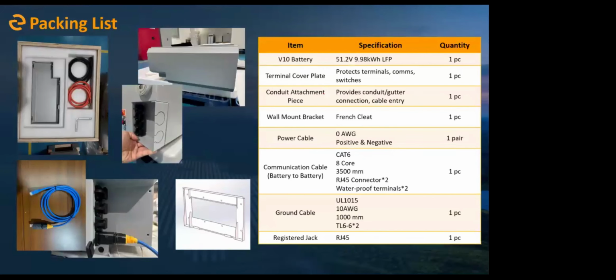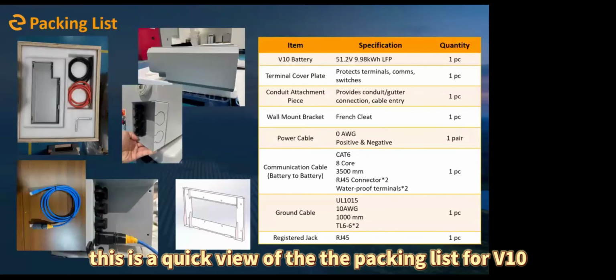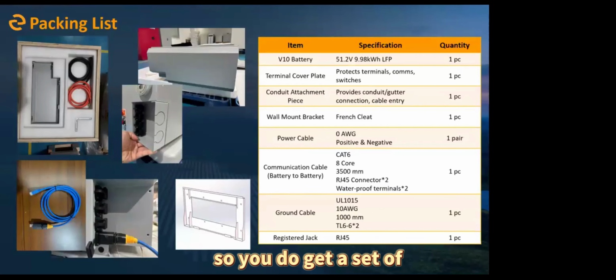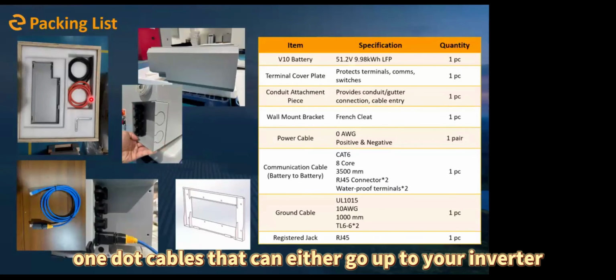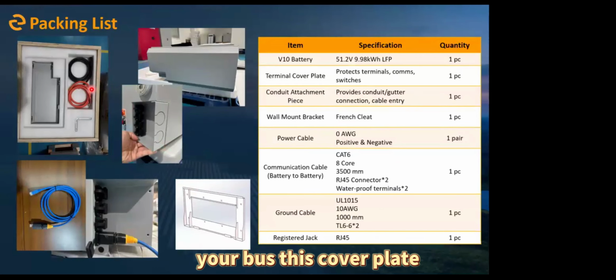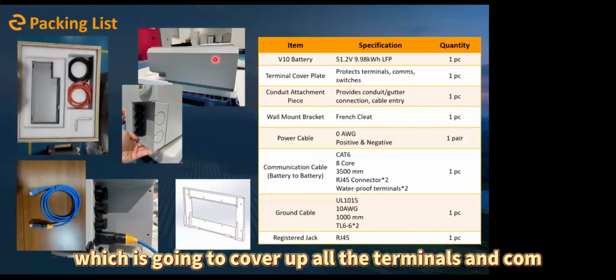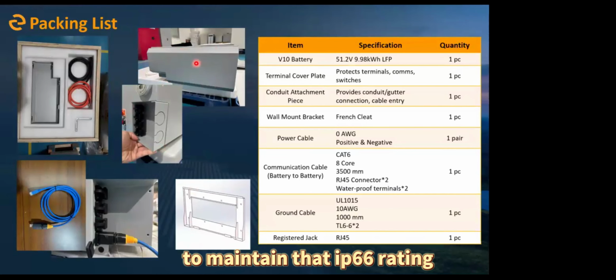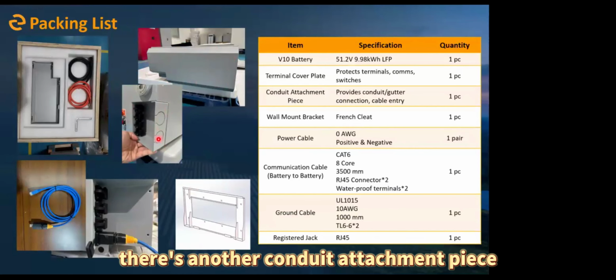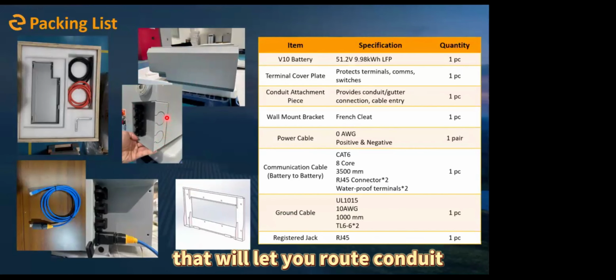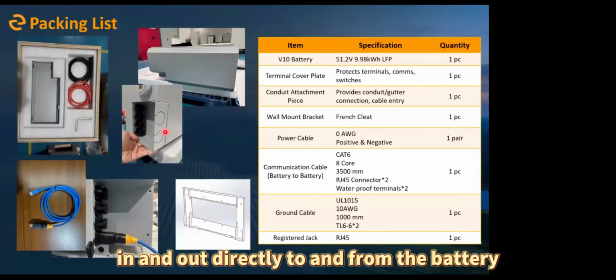This is a quick view of the packing list for the V10. You get a set of 1-aught cables that can go up to your inverter or your bus, and this cover plate, which covers up all the terminals and comms port on the battery to maintain that IP66 rating. When doing an outdoor install with this cover plate, there's another conduit attachment piece included that lets you route conduit in and out directly to and from the battery.